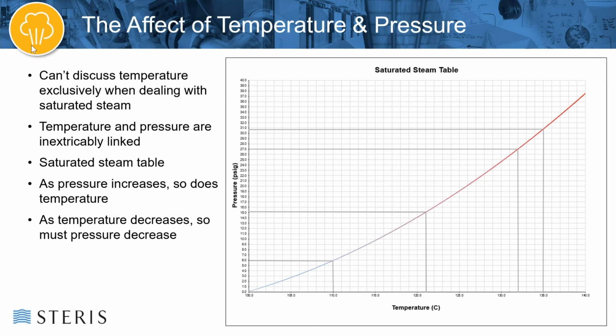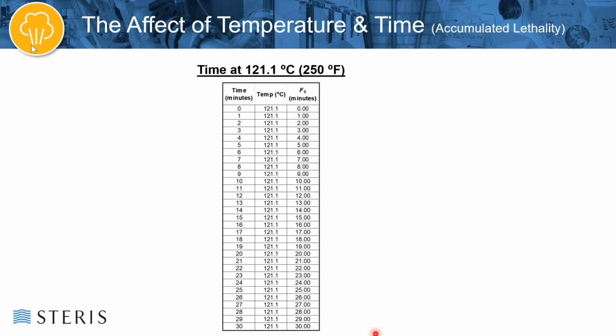What happens when we talk about temperature and time? When we talk about temperature and time combined, this is essentially what's called accumulated lethality. The shorthand for accumulated lethality is F sub 0. Some of you might have heard that term thrown around and wondered, what is F sub 0? Well, it's accumulated lethality. And typically, F sub 0 keys in on a universal reference point of 121 degrees C, which is just kind of, at some point someone decided that 121.1 C, which is 250 degrees Fahrenheit, is going to be the primary reference point for steam sterilization.